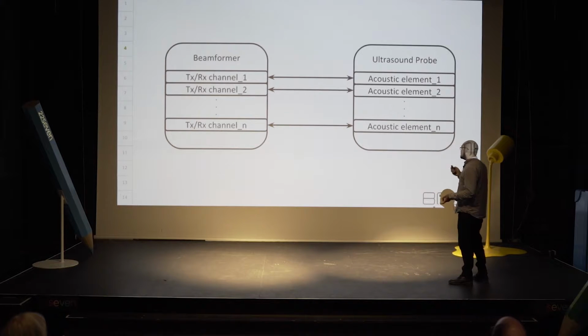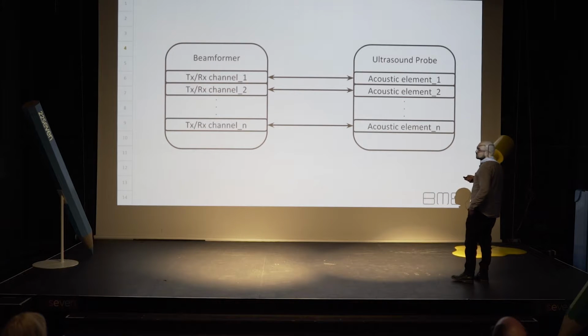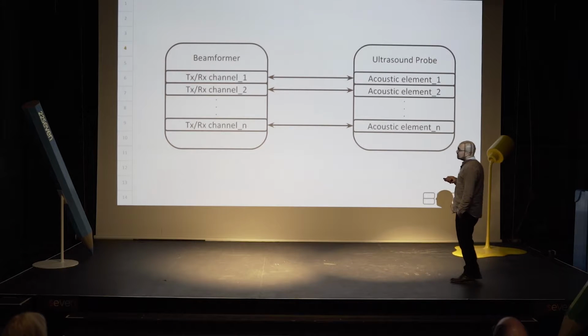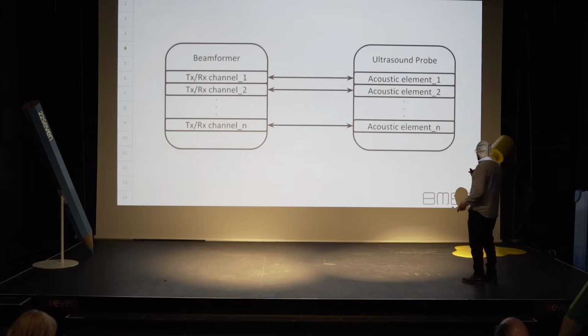So to return to our challenge of trying to make that probe longer, we could fairly easily add more acoustic elements to the ultrasound probe, which would make it longer. But the limiting factor in this setup is the number of transmit and receive channels available in the beamformer. So that gives us two potential solutions, and that is to either find a way to increase the number of transmit and receive channels or to widen the acoustic elements themselves.